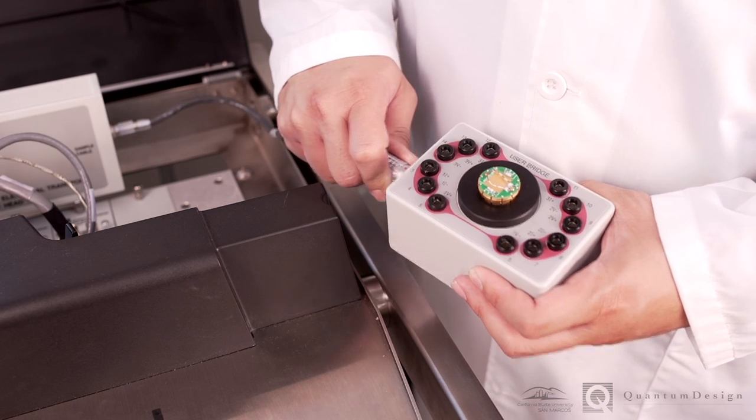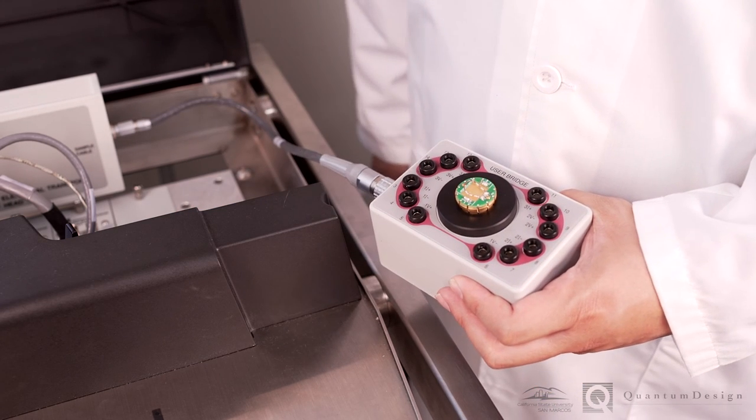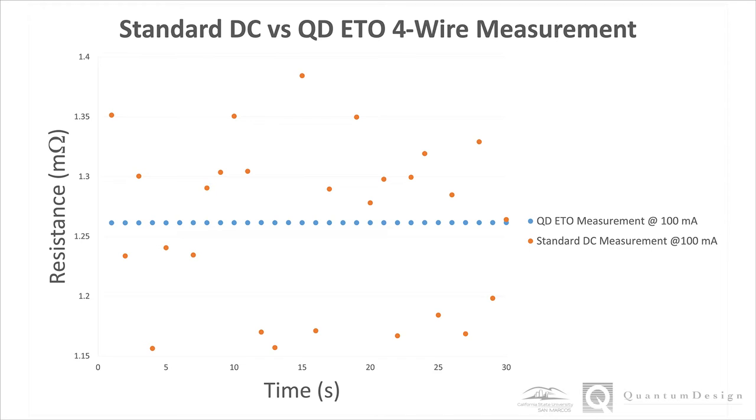Now we will perform a 4-wire measurement on the copper wire using the ETO module and compare that to measurements obtained using a standard DC source and voltmeter. We take a reading every second. When you compare the standard DC measurement in orange to the Quantum Design ETO measurement in blue, you can see that the ETO performs a far less noisy measurement at this level.